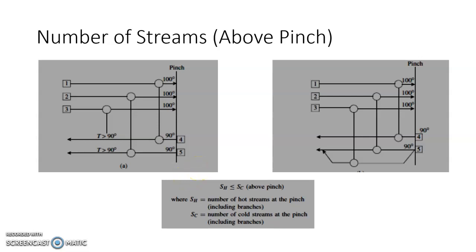In the previous video, we saw that while designing a heat exchanger network, in the grid diagram we represent above-pinch and below-pinch regions. Above pinch, the number of hot streams has to be less than or equal to the number of cold streams, because every hot stream at the pinch requires a corresponding cold stream at the pinch to maintain delta T minimum. If there are fewer cold streams, we split cold streams until the numbers are equal.